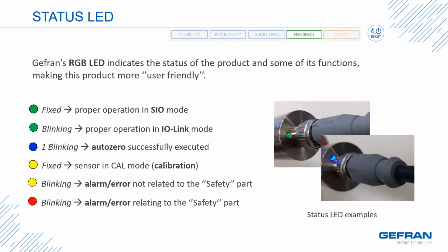On the housing of the sensor is a multicolor LED. It will give indication of the current status of the sensor. For instance, fixed green, the sensor is in the standard IO mode. Blinking green, the sensor is in the IO-Link mode. A single blink of blue indicates the auto zero was successfully executed. Solid yellow, the sensor is in a calibration mode. Yellow blinking is an alarm or an error not related to safety, if the safety features are included. Red blinking is an alarm or error that is relating to the safety, if the safety features are included. This gives the ability of an operator or maintenance person, if the sensor is visible from their location, to see its current status.